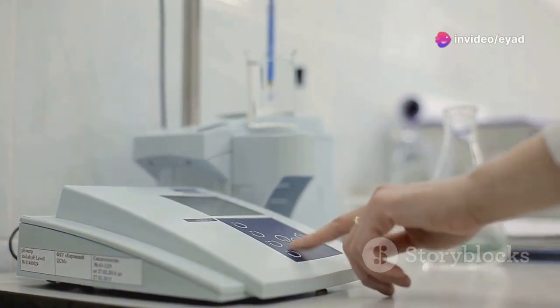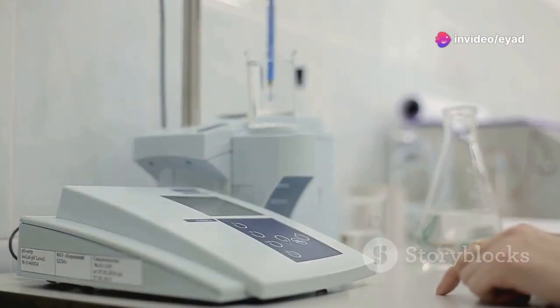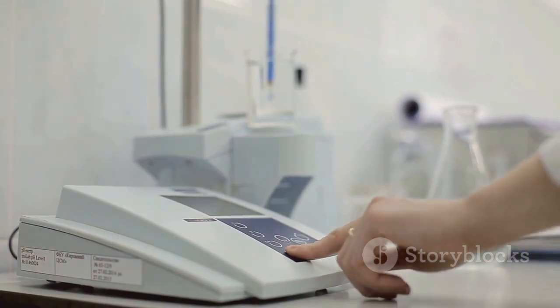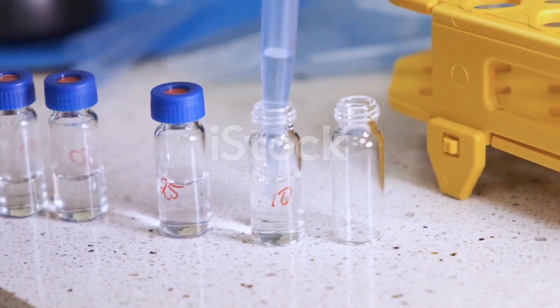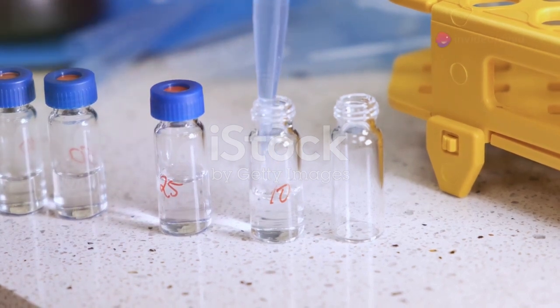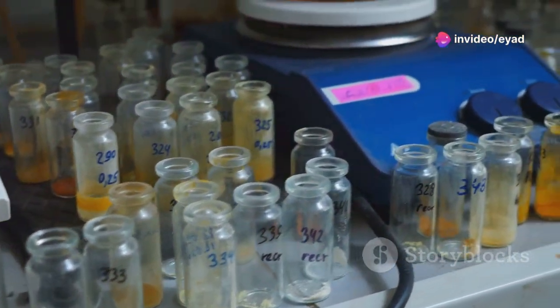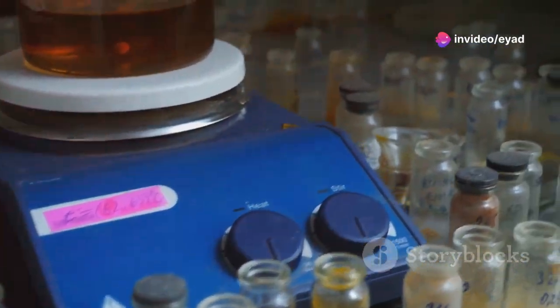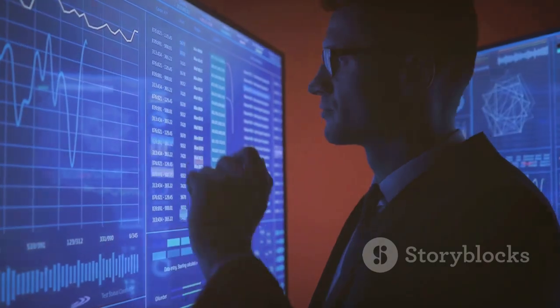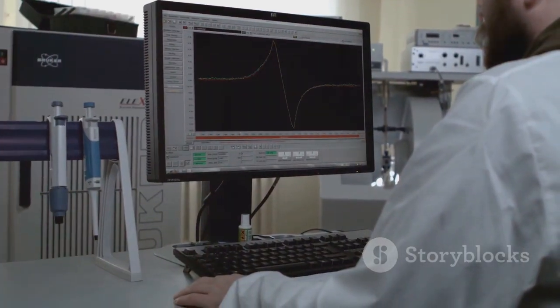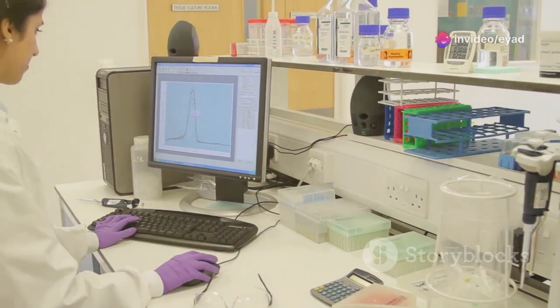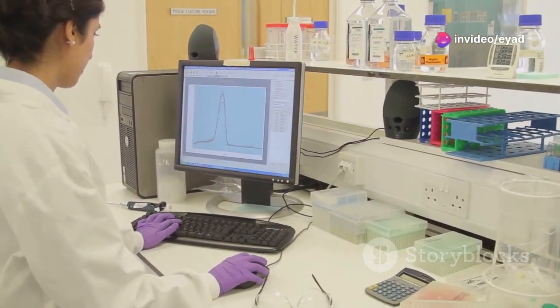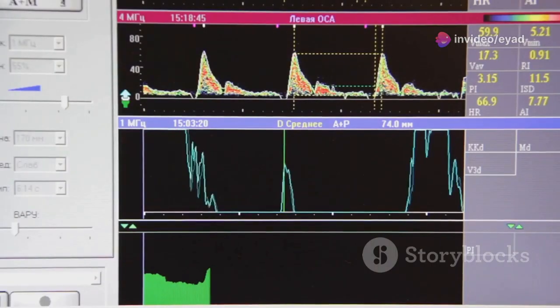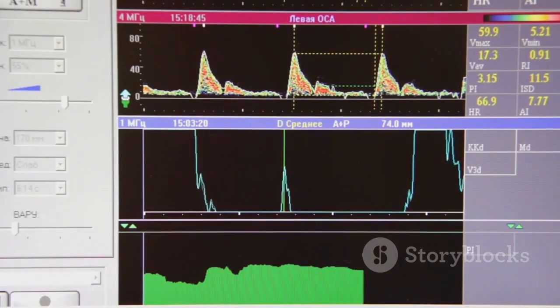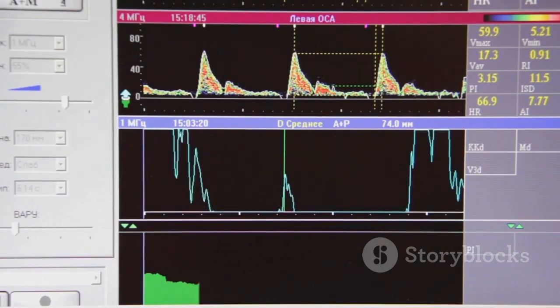Building trust, the art of creating calibration curves. Creating a calibration curve is like teaching a sensor to speak the language of the biological parameter it's measuring. This involves exposing the sensor to a series of known standard solutions or stimuli. These standards serve as benchmarks, providing known values of the parameter being measured. As the sensor is exposed to each standard, its output signal is carefully recorded. This data is then plotted on a graph with the standard values on the x-axis and the corresponding sensor output values on the y-axis. By connecting these data points, we obtain the calibration curve, which represents the unique relationship between the sensor's output and the actual biological parameter.